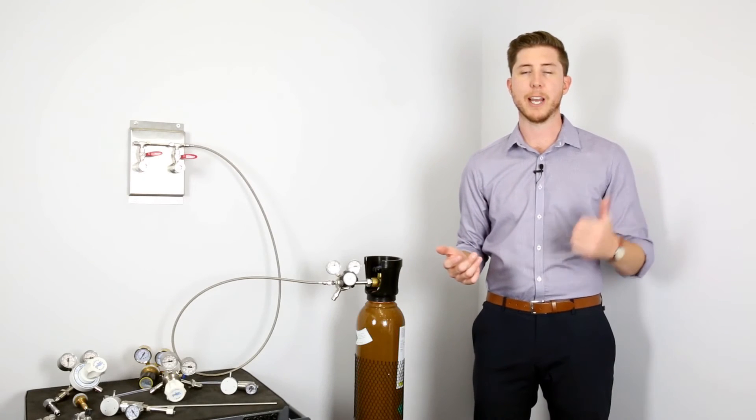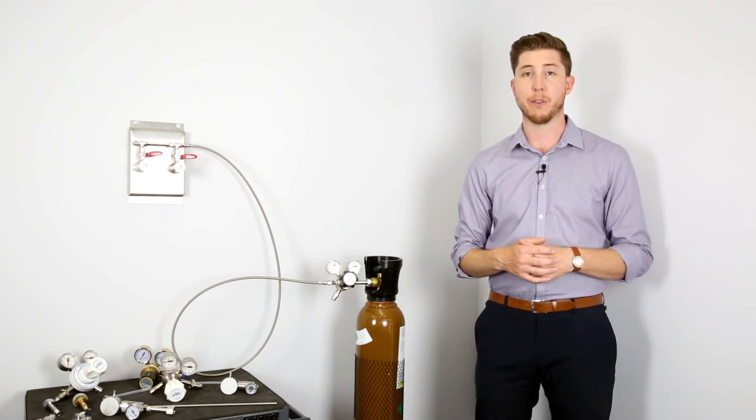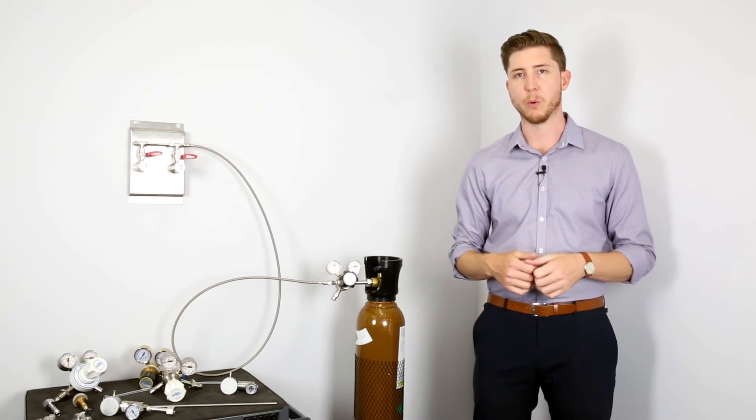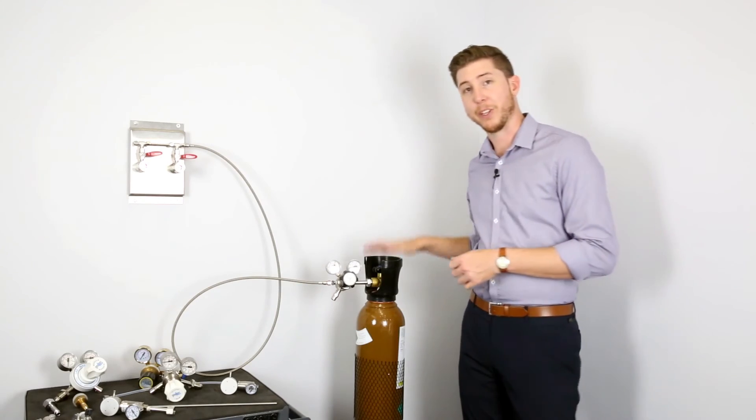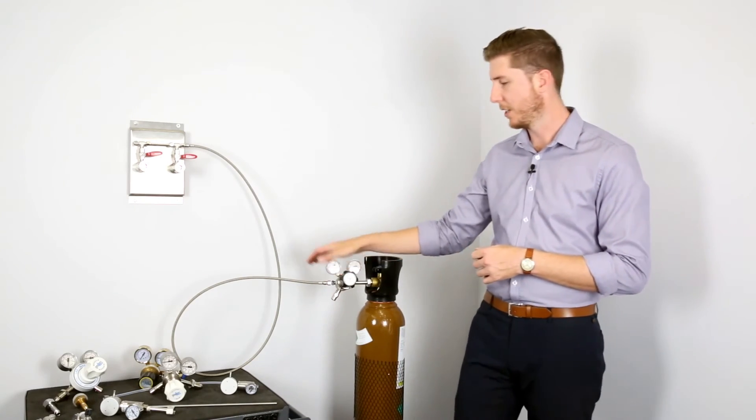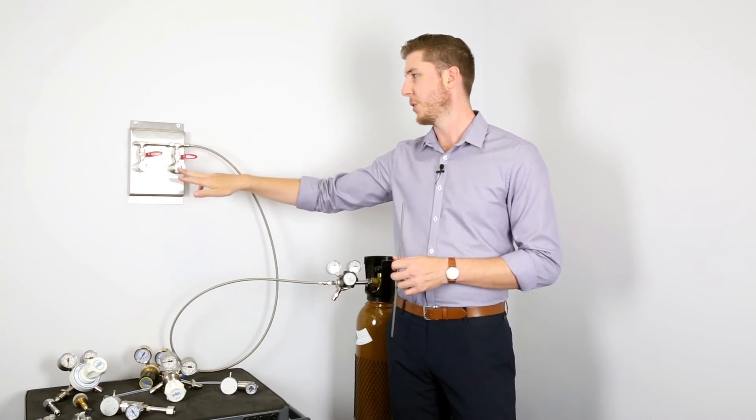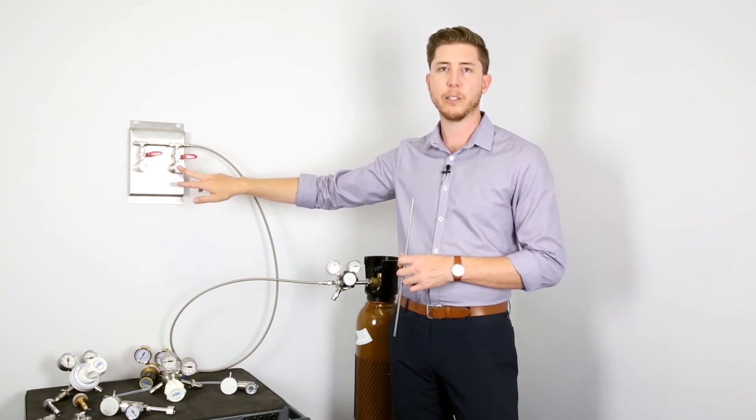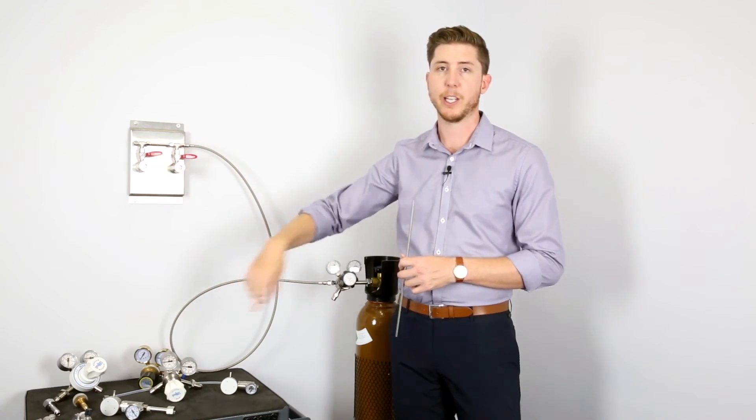If you would like to store your gas cylinders outside the room or at a greater distance than three meters a long run system will be required. A long run system consists of a gas cylinder, a pressure regulator, stainless steel tubing either flexible or rigid and an outlet panel. Here is where you'll screw in your point of use regulators and some soft tubing to connect down to your docking station.